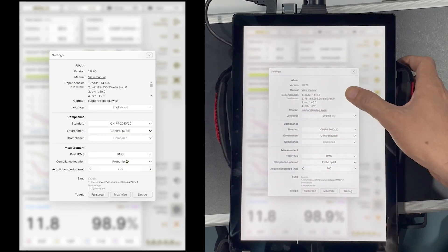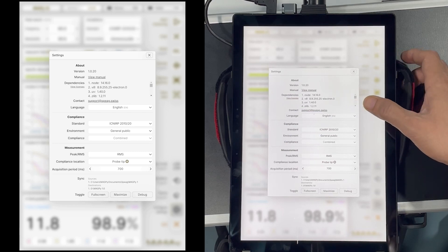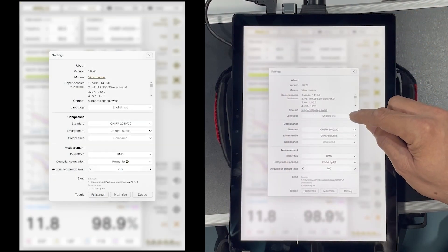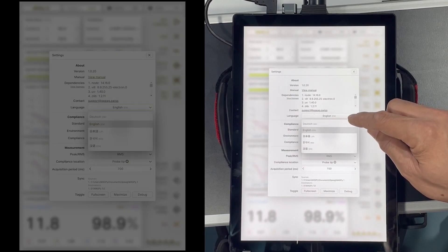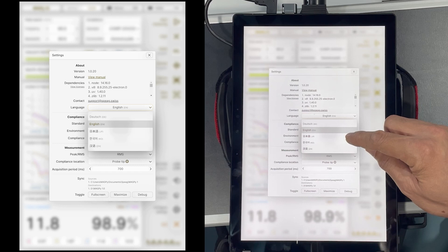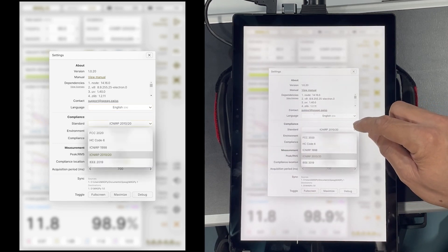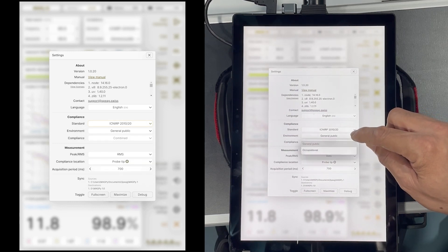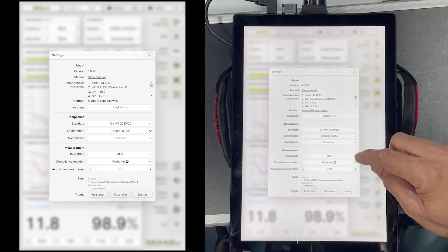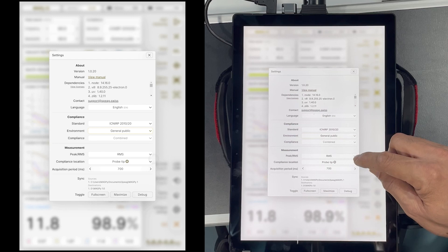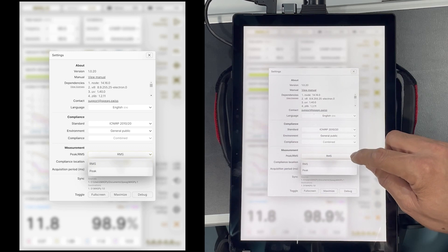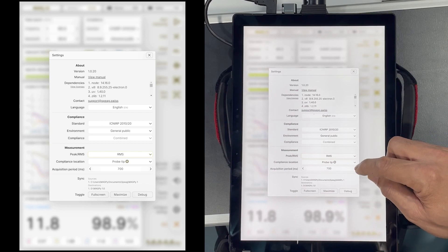The configure settings button allows to adjust software settings. These settings include information about the software version and the version of the components, a link to the user manual, language of operation. SPIAG already supports English, Dutch, Japanese, Korean and Mandarin. Default compliance standard and the exposure situation, evaluation at the probe tip or the center of the probe, type of detector, RMS or peak for the fields shown in the incident windows, signal acquisition time for data point, and also options to switch the screen from full screen to the maximum modes.